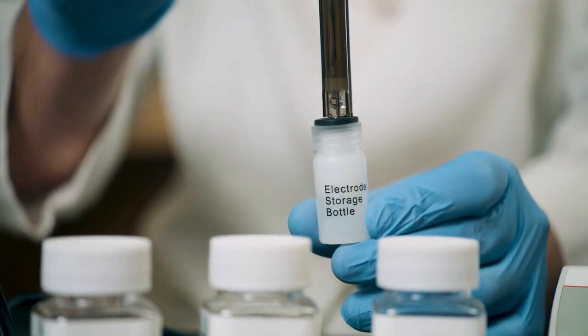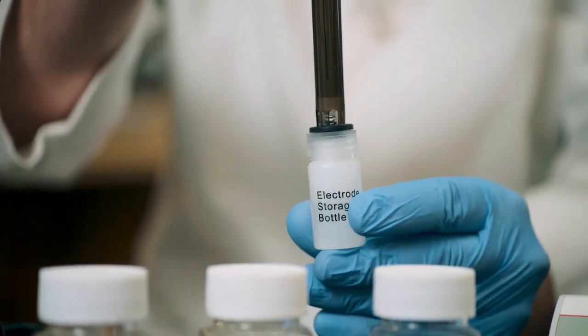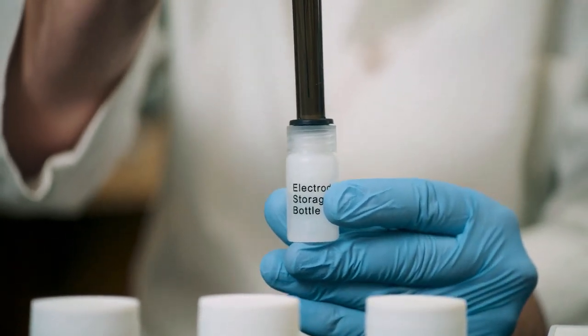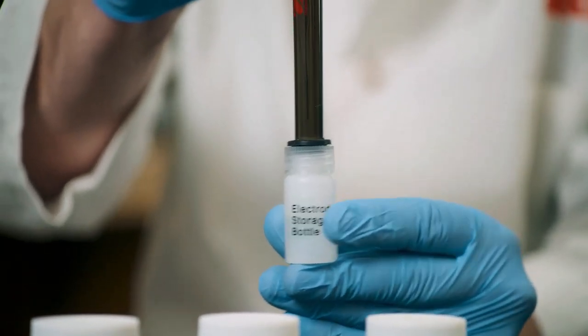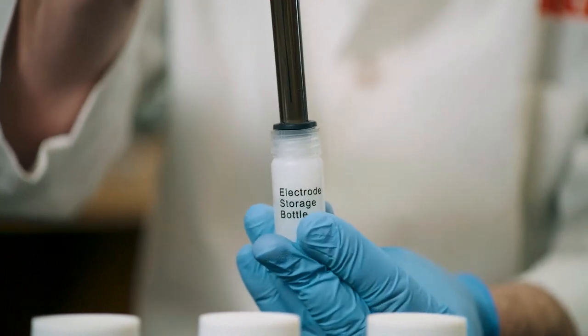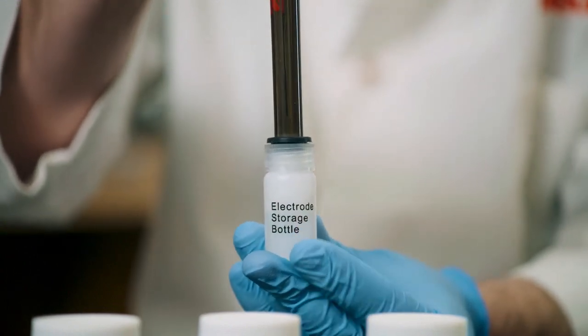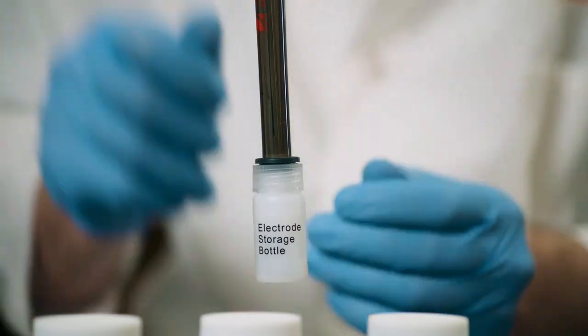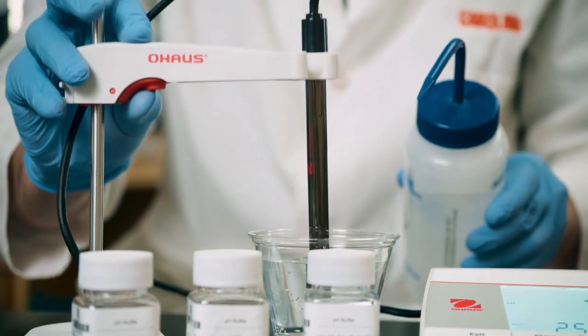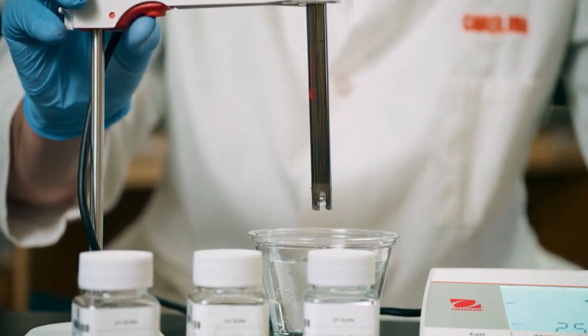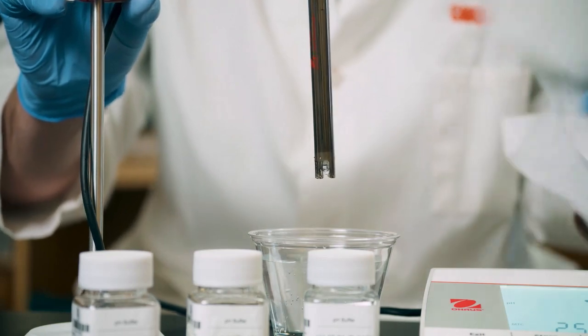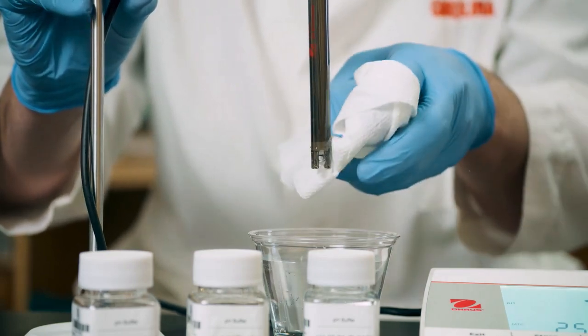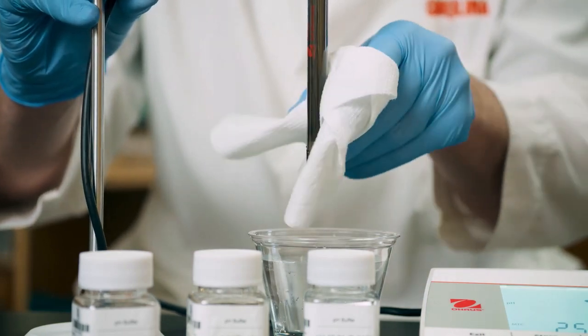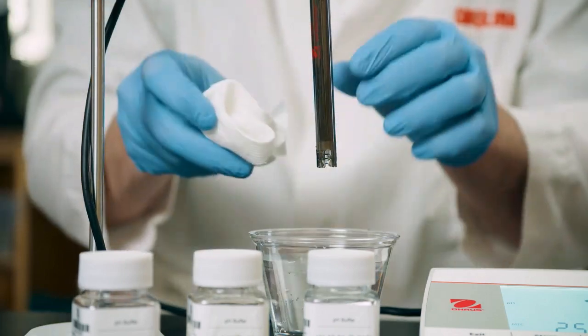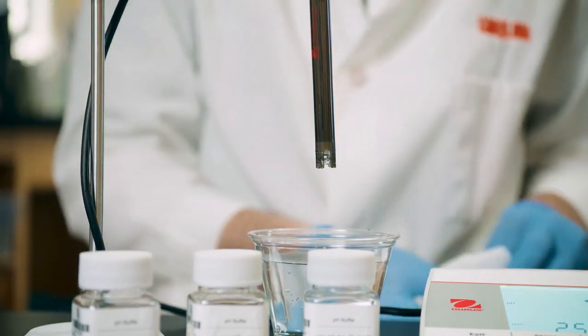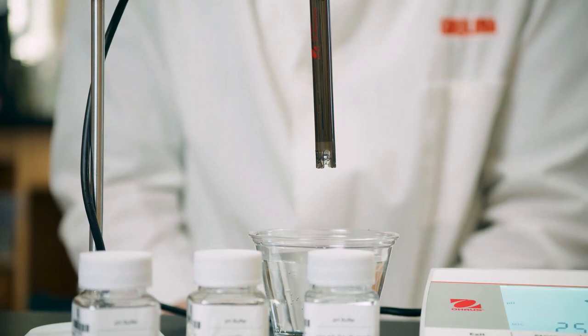The pH electrode should always be stored in a storage bottle containing electrode storage solution. This prevents the bulb of the pH meter from drying out and damaging the pH meter. Always keep the electrode immersed in its storage solution. Before and after using a bench meter to test a solution, rinse the pH electrodes with pure distilled water and wipe clean to prevent leftover solutions from causing inaccurate results. Like pen meters, bench meters also require periodic calibration to ensure accurate readings.